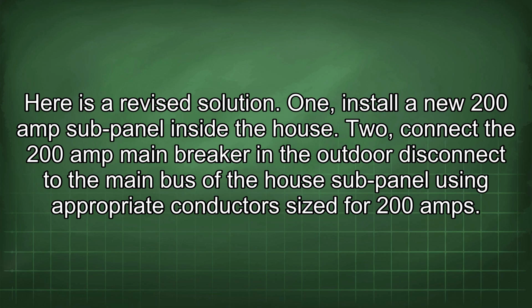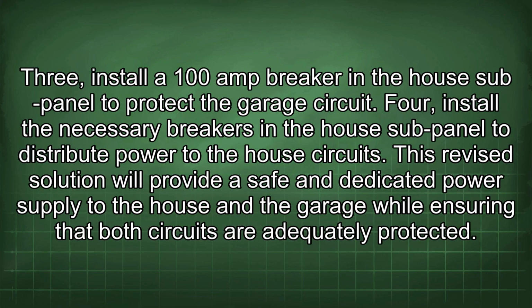1. Install a new 200 amp sub-panel inside the house. 2. Connect the 200 amp main breaker in the outdoor disconnect to the main bus of the house sub-panel using appropriate conductors sized for 200 amps. 3. Install a 100 amp breaker in the house sub-panel to protect the garage circuit. 4. Install the necessary breakers in the house sub-panel to distribute power to the house circuits.